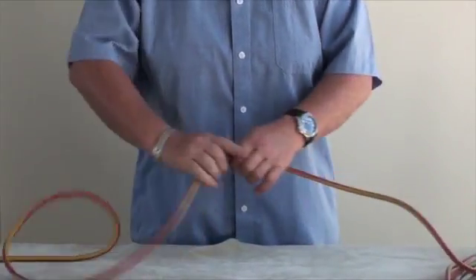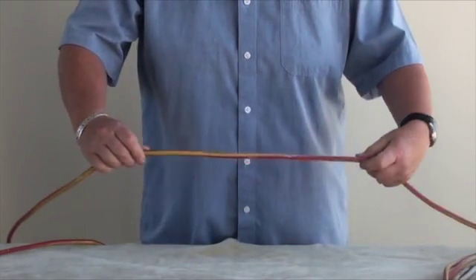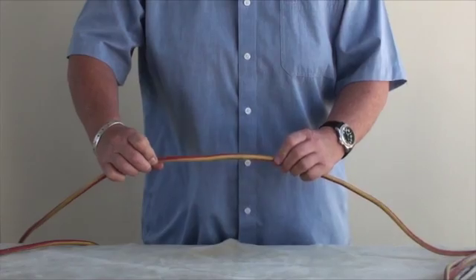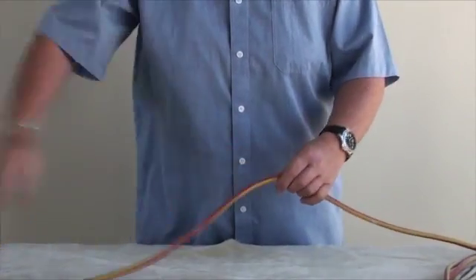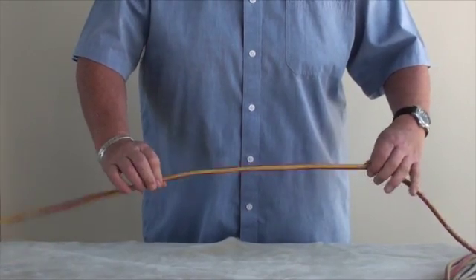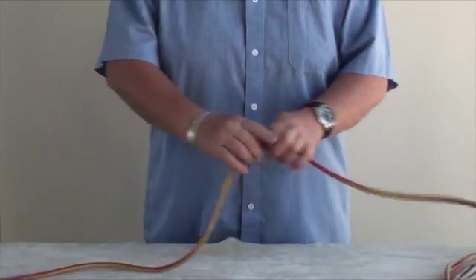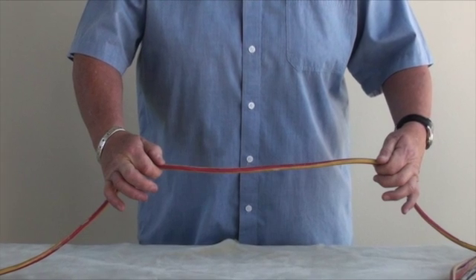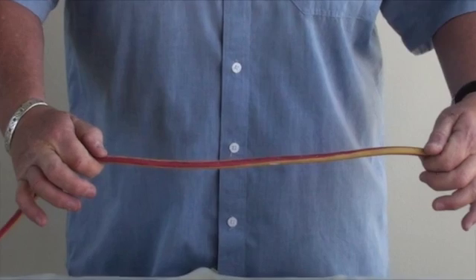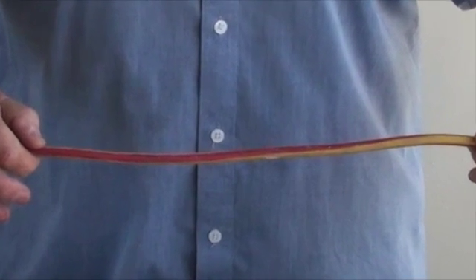Whilst you are doing this, you are feeling and looking for cuts, burns, or melted sections that have gone through the outer insulation to the inner coloured insulation. Rotate the cord 360 degrees as you move down the cord. This part is performed slowly to ensure small but dangerous splits are picked up at this stage.